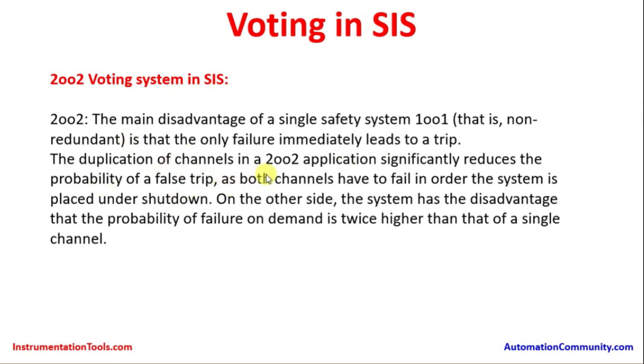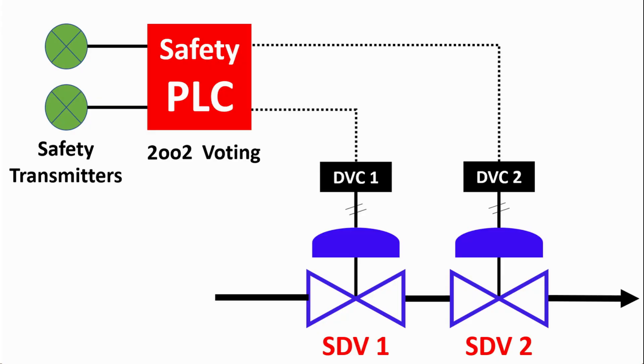In a 2 out of 2 application, the duplication of channels significantly reduces the probability of a spurious trip, as both channels must fail in order for the system to be placed under shutdown. On the other side, the system has the disadvantage that the probability of failure on demand is twice as high as that of a single channel. In the 2 out of 2 configuration, the process pipe feeds through two valves in series — both must close for the process to shut down and trigger a safety trip.